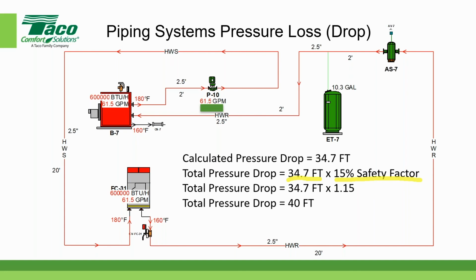So here's where it becomes a bit subjective. You can put in any reasonable safety factor that you want. The calculation is based on pure numbers, there is no fluff in the actual calculation, but this is when we go from a calculated value to the total pressure drop in the system. Some people might pick 10%, other people might pick 20 or 25%, and you can see it becomes somewhat subjective. So the total pressure drop was equal to 40 feet.